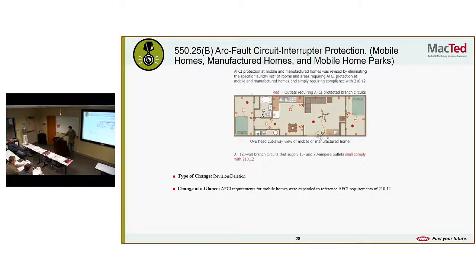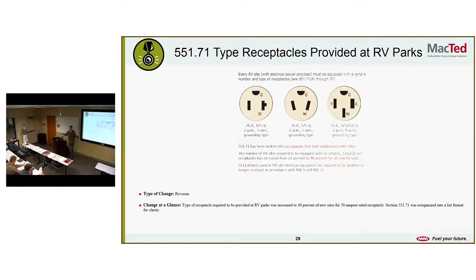Arc fault circuit interrupter protection, so AFCI. Arc fault protection at mobile homes and manufactured homes was revised by eliminating the specific laundry list of rooms and areas. And now they simply require compliance with 210.12. Put an arc fault in. Pretty much looks like everywhere. Those are already death traps. Might as well try to make them a little bit safer.